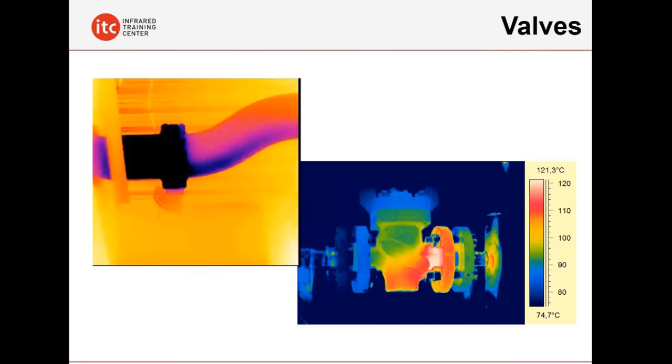Valve operations. A valve that was in the open position. It was actually physically open. It visually confirmed it was open. But with infrared, we can see that the valve actually appears to be closed. Something that we can use infrared for very nicely, or possibly a leak or a bypass.